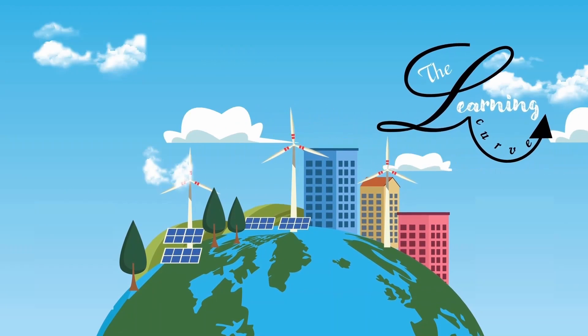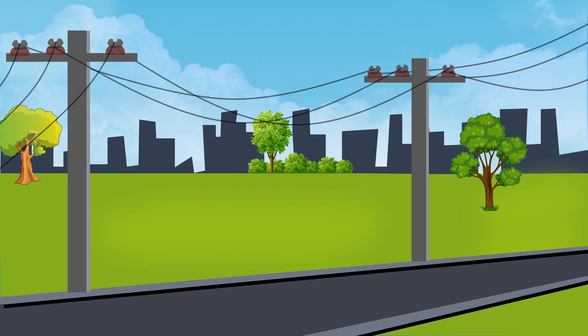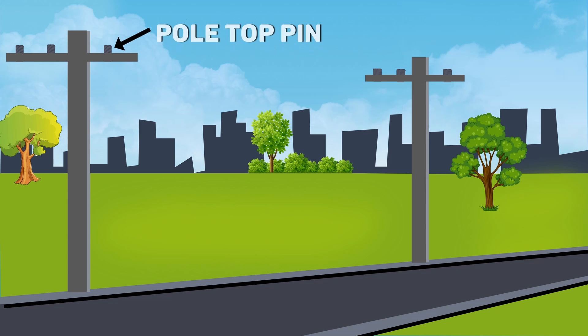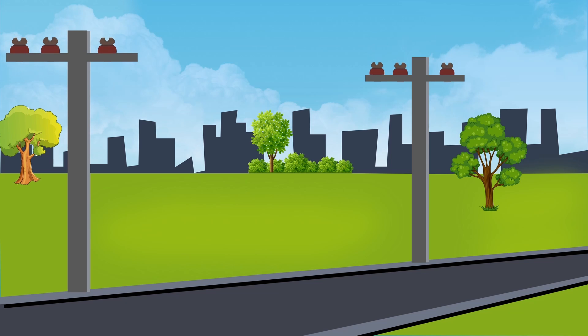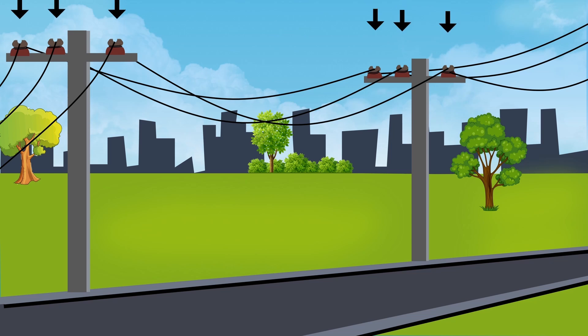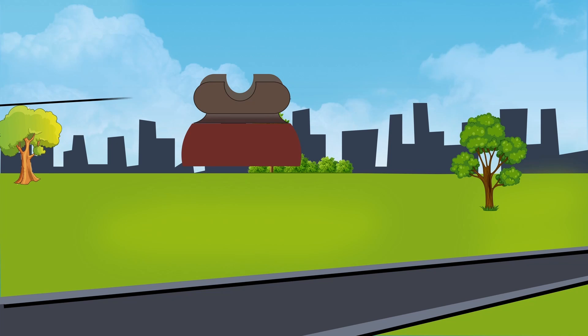Hi, I am Benila and you are watching The Learning Curve. Let's start with the pin type insulators. Pin type insulators are mounted on the cross arms of the poles with the support of pole top pins. A lead thimble is cemented into the insulator body to receive the pin. If you look at the top of the pin insulator, you will find a groove, or in other words, a narrow cut on it.